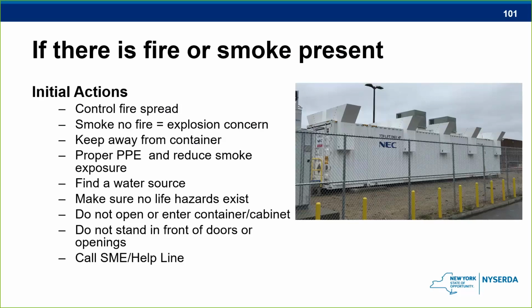You're not saving anything. It's kind of like a car fire. When's the last time you saved a car in a car fire? You just don't do it. That car is demolished. The same with this. And the installers know that. And the installers are starting to realize, like, look, you're not saving our property. These things got to be removed anyway. So what we would try to do is make sure that the heat being transferred out of the enclosure doesn't go to the adjacent enclosure and get that one to go on fire. So basically, you're putting up a protection line. That's what you're really doing.